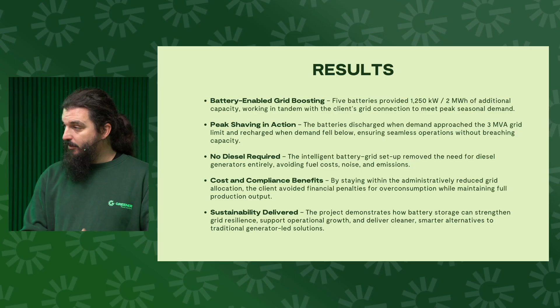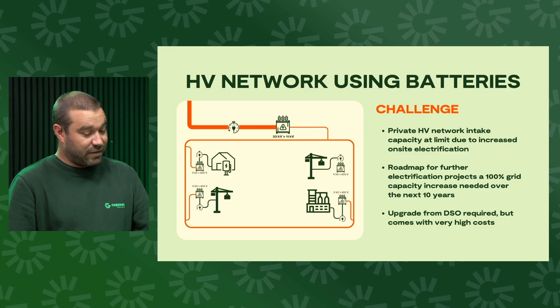This case ends up with multiples of what Robin was just describing, but it's more to do with a private HV network or private wire network. The specific challenge was due to the network intake being at capacity, but the site had a roadmap to increase electrification of equipment by over 100%, so they needed to double their intake. That comes at a very large cost to double these high or medium voltage intakes from the DSO, so they came to us to see if there was something we could do to help.